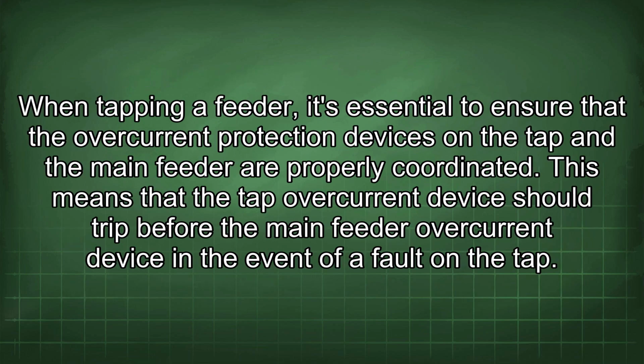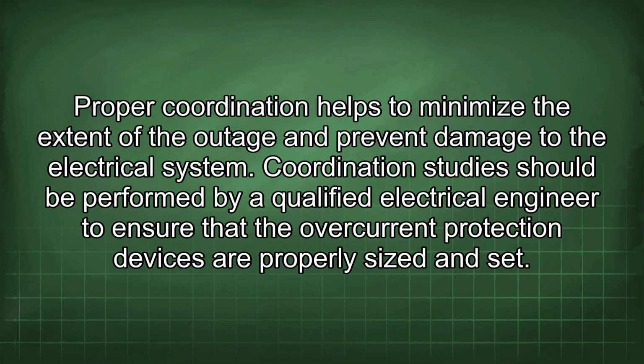When tapping a feeder, it's essential to ensure that the overcurrent protection devices on the tap and the main feeder are properly coordinated. This means that the tap overcurrent device should trip before the main feeder overcurrent device in the event of a fault on the tap. Proper coordination helps to minimize the extent of the outage and prevent damage to the electrical system.